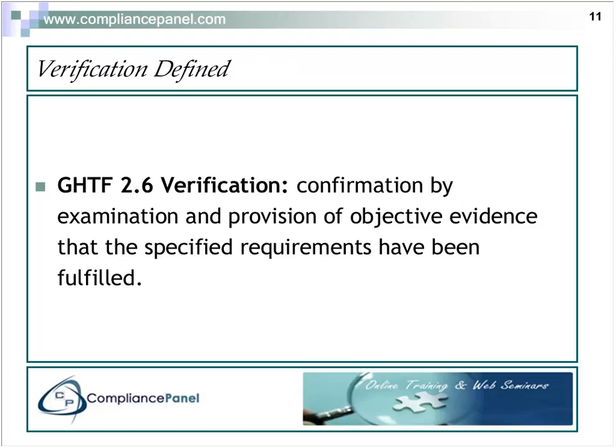Now, in the GHTF document also, another definition is verification, and that's confirmation by examination and provision of objective evidence that the specified requirements have been met or fulfilled. So again, we have to provide objective evidence, and the process that we use is some type of examination that can be an inspection, a test, or other observation that we can demonstrate that a requirement for a particular product has been met. And of course, we talk about design verification. We talked about that earlier.